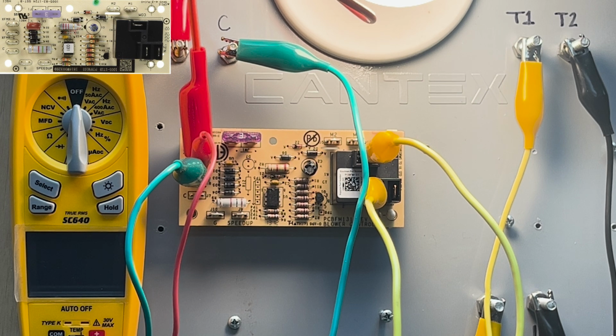But this is how you get efficiency in the very beginning. That 7-second delay when the coil is coming on, it's getting either warm or cool depending on what mode it's in, heat or cool. That off delay is the same thinking. You're just getting more dehumidification, more comfort out of the back end, because that coil is at a higher or lower temperature than the air moving across it. So why not take advantage of that with the compressor off?